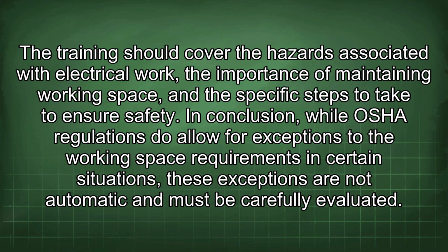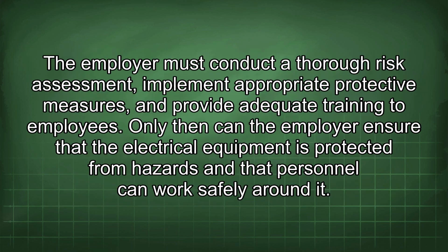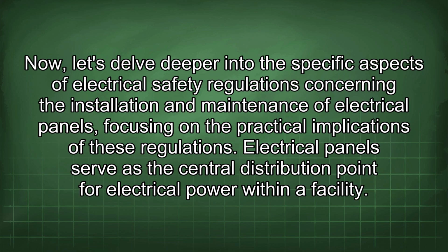In conclusion, while OSHA regulations do allow for exceptions to the working space requirements in certain situations, these exceptions are not automatic and must be carefully evaluated. The employer must conduct a thorough risk assessment, implement appropriate protective measures, and provide adequate training to employees. Only then can the employer ensure that the electrical equipment is protected from hazards and that personnel can work safely around it. Now let's delve deeper into the specific aspects of electrical safety regulations concerning the installation and maintenance of electrical panels, focusing on the practical implications of these regulations.